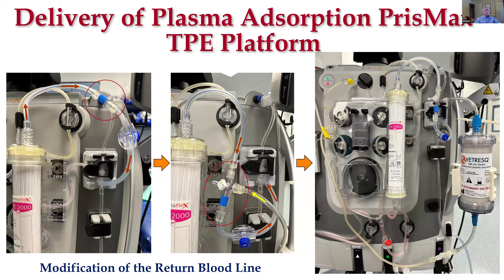The other modification you have to do is you have to reroute the replacement line. The replacement line from your replacement bag, which sits here, comes up through this pump, I guess, and then goes directly into this chamber, at this bottom pump. And this is something that you also have to do aseptically, because this is directly into the patient's blood. And there are two ways of doing this. One, if you have one of these line clamps, which we have on the Opti machine, or you get one from your hematology unit, you can just heat seal the replacement line here.